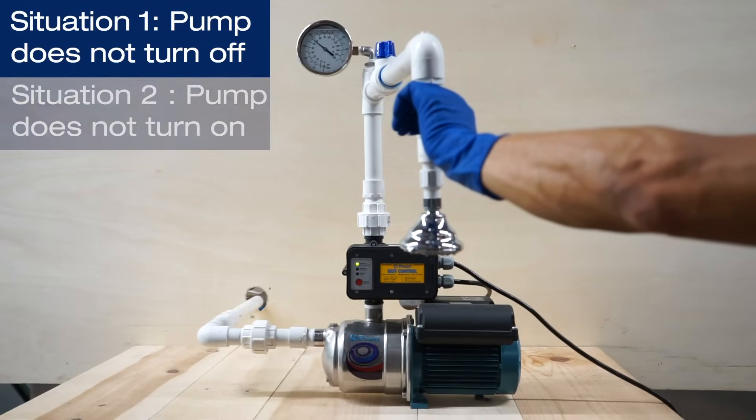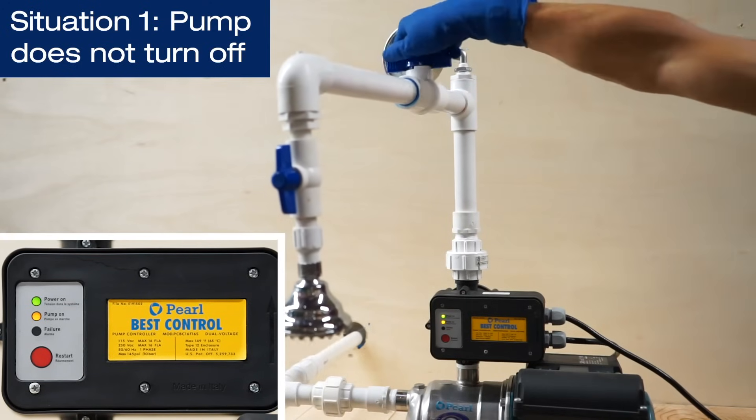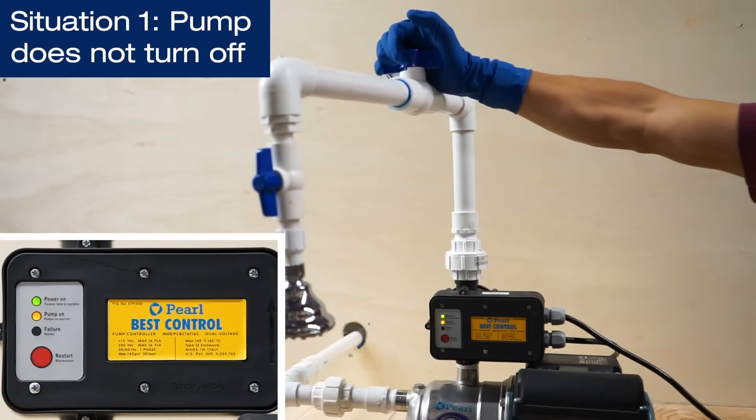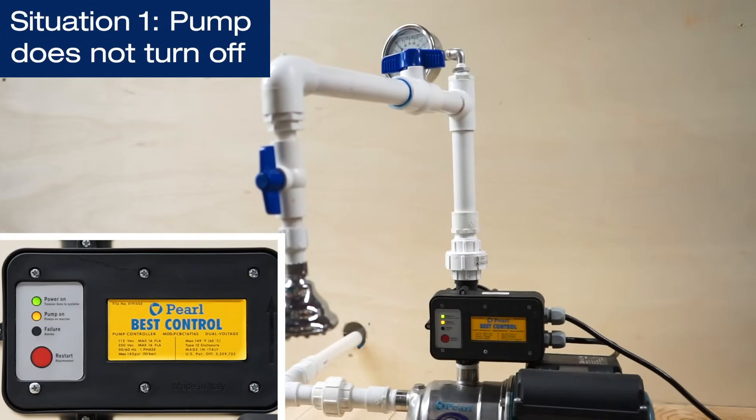For the first situation, in which the pump does not turn off, if there is no tap or faucet open and the system is working, then the pump should shut off just a few seconds after you close the ball valve. If this happens, the system is working perfectly, which means there might be a leak elsewhere in the installation.